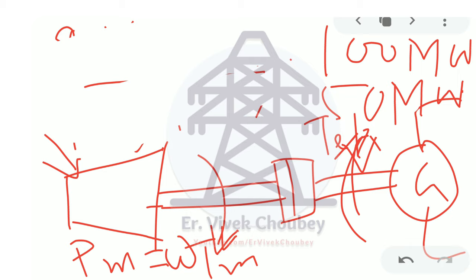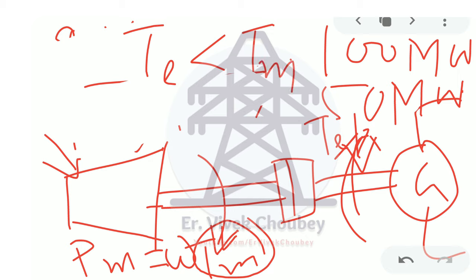But the mechanical torque will not decrease. Why? Because we don't know that there is a decrease in demand, and we are still providing the same steam. So eventually, this mechanical torque will be greater than the electrical torque. And this is the point of the whole problem. The electromagnetic torque will be less than the mechanical torque, and because of that, the mechanical torque will dominate the whole system, and that will cause a sudden jerk and sudden acceleration in the whole turbo generator system. Now, acceleration means there is a rise in omega. Okay. Now, why is it problematic? Let me clear this all.